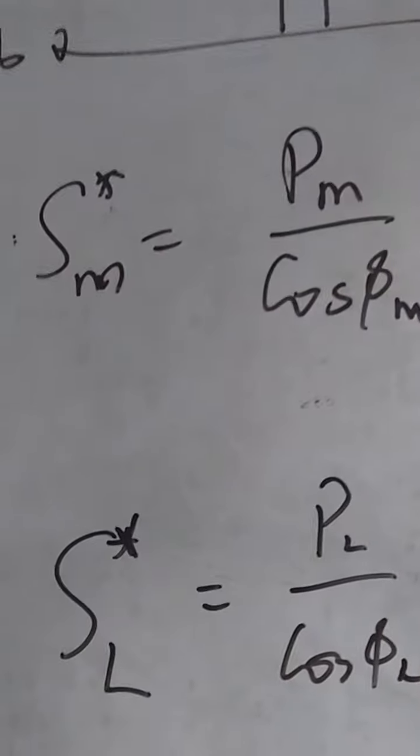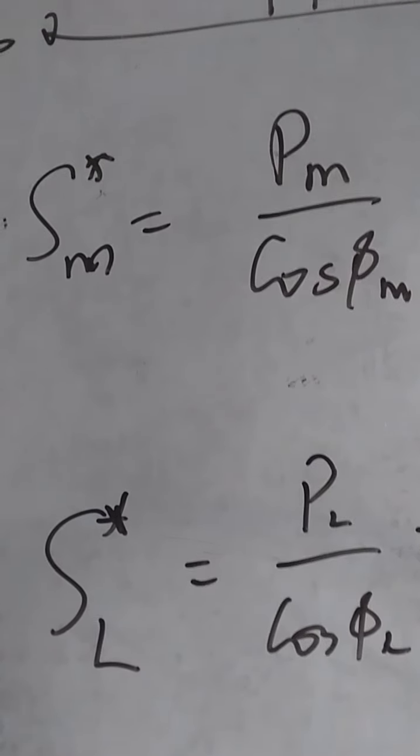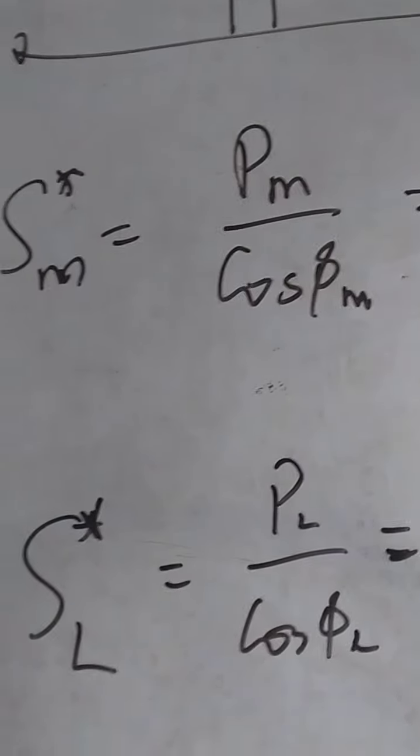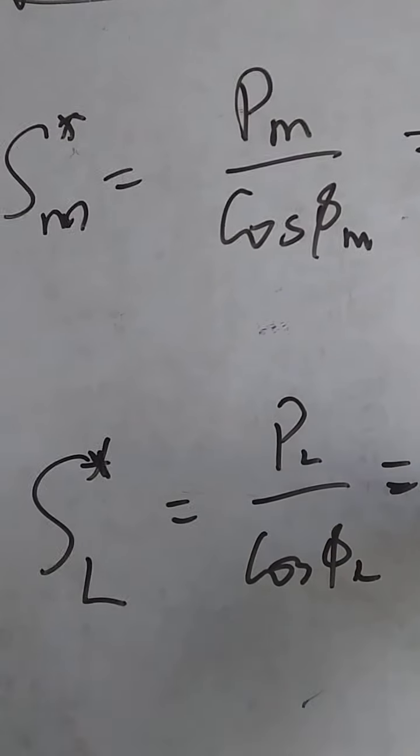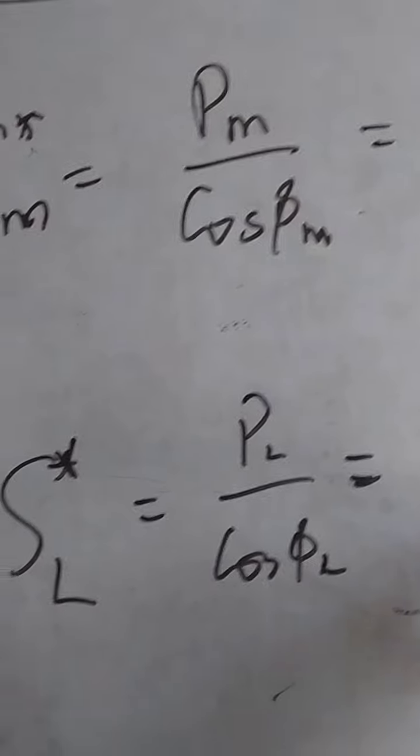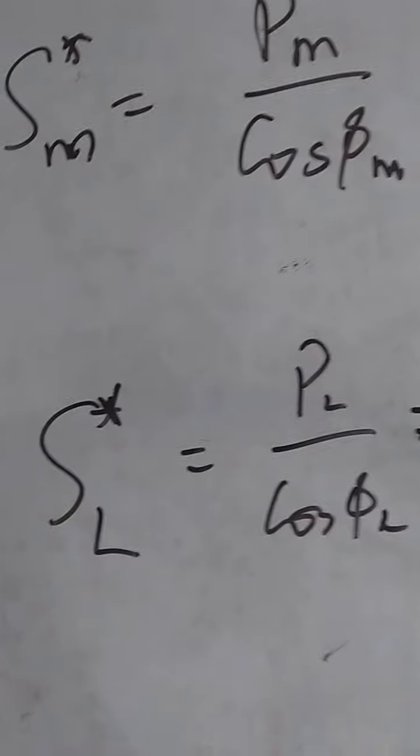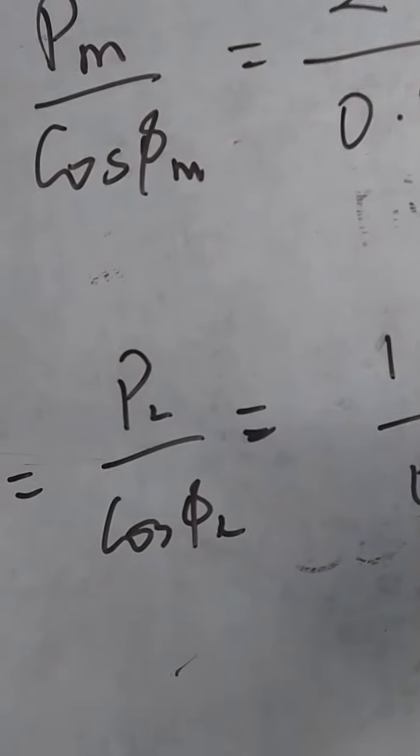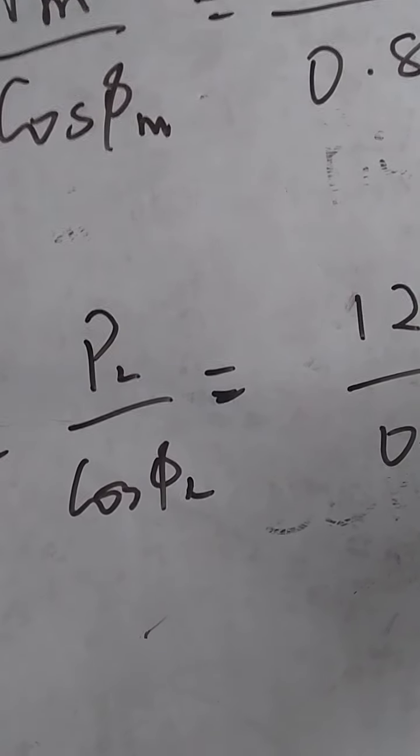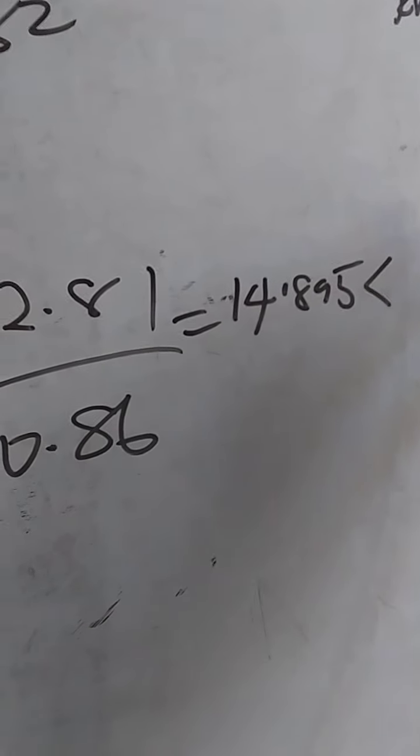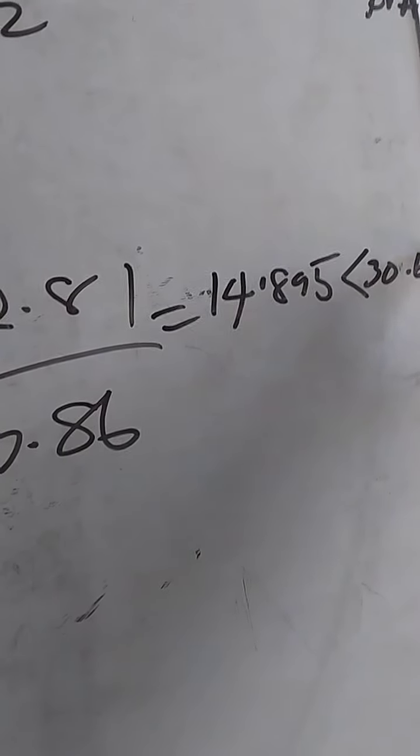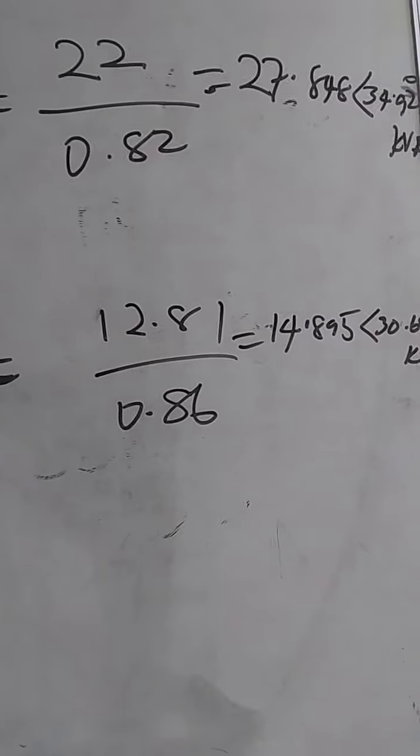The input into that one is 12.81, that is the power that is drawn by that load. So, that will be 12.81 over the power factor as given 0.86. This will give you the capacity of that load to be 14.895 at angle 30.68 degrees KVA. So, that is the capacity of that.